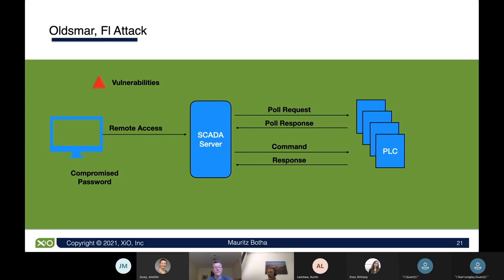So let's get back to these vulnerabilities. What happened at Oldsmar in Florida? I mentioned the old architecture, and I want to delve into that a little deeper. Right in the middle, you've got a SCADA server, and the SCADA server sends a poll request to a programmable logic controller, the PLC, and it responds to the poll. It can also send a command, and the PLC will respond to a command. On the left, we may have remote access or a need for remote access.